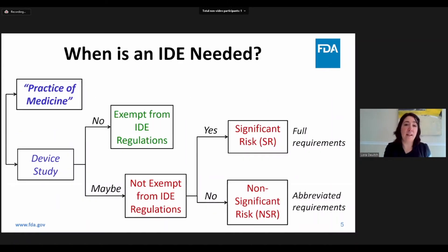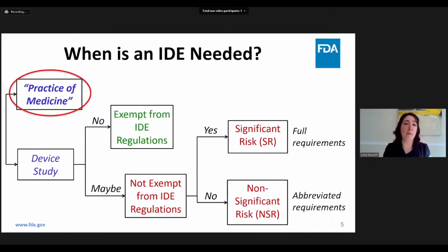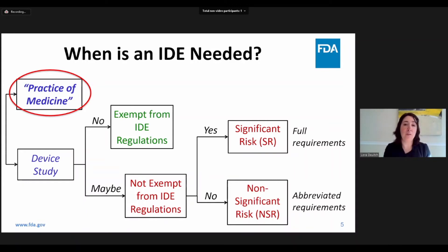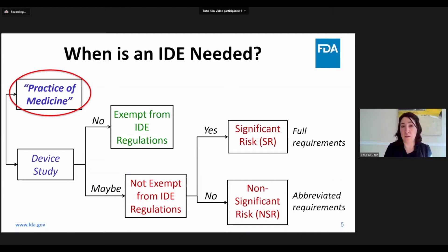So when is an IDE needed? The first question is: are you conducting an investigation or study, or are you treating a patient under the practice of medicine? Since this workshop focuses on new and innovative technologies, I will not spend much time discussing practice of medicine. However, it is important to note that practice of medicine means a legally marketed device can be used outside its approved indications by a physician to care for a patient, as long as it is not used in a clinical trial or investigation.